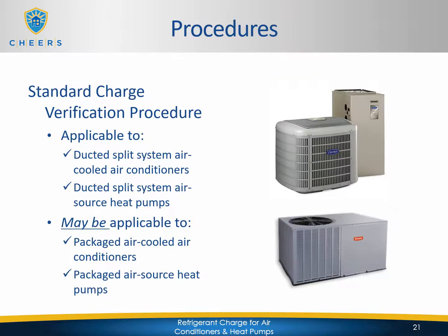The standard charge verification procedure is applicable to ducted split systems air-cooled air conditioners, ducted split systems air source heat pumps, and it may be applicable to packaged air-cooled air conditioners and packaged air source heat pumps.